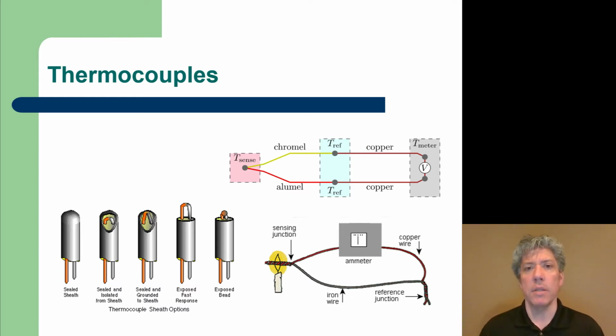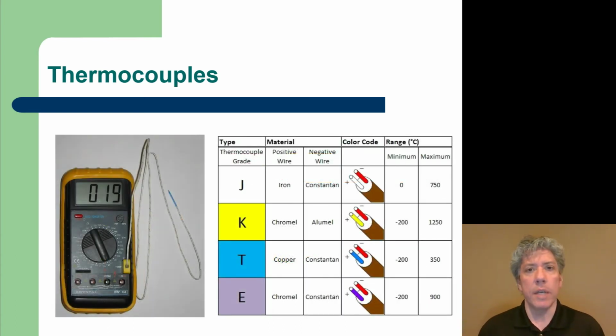Now, it's common to use a thermocouple welder, which is usually just a small thing. It's not like a welder like you'd use for stick or MIG welding, but it's just a small welder where you put the two wires in, usually a desktop unit. It generates a high voltage, and a very small bead melts together of the two materials, and that's the sensing junction. And typically you want that bead to be small so that it has very good response characteristics, and it doesn't take forever to heat up a glob of weld, and so your thermocouple responds rapidly. Grounding is not always a consideration.